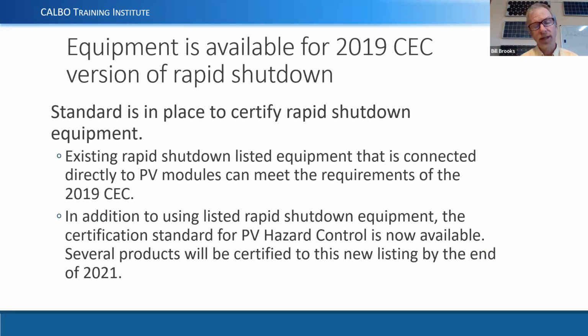That would include things like the Tesla listing requires a mid-circuit interrupter that they use. It's kind of like an individual module switch, but it interrupts midway in the unit in the system. They might have a couple of those in a PV array, depending on the array design, things like that. And so those individual units are going to be rapid shutdown equipment listed, and then they're specified as specific products that have to be used in the PV hazard control system.